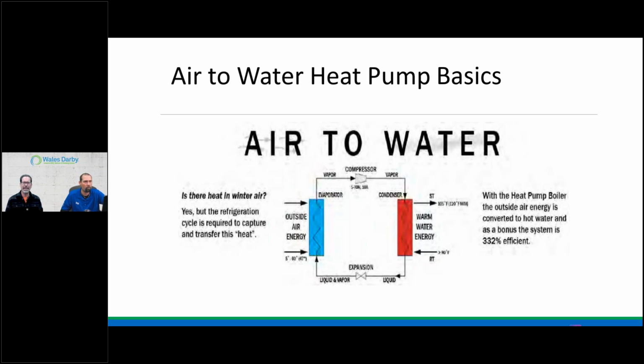So if Mother Nature provides us heat, even in, let's say, subzero temperatures, the technology we have in our equipment now, through electrified compression, refrigerant, achieves really high efficiency, but the give up is lower water temperature. So the other side of the game is, we just have to marry what we can maximize, 120 let's say, to maybe something we've been doing for the last 60 years: grossly oversizing all our emitters?